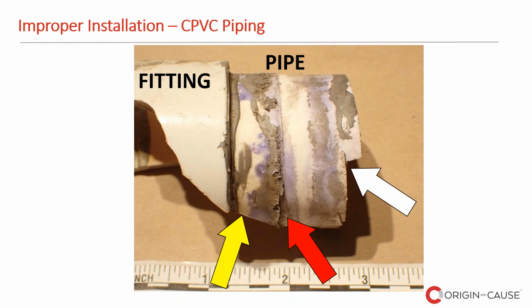In this case, you can see here with the red arrow, basically that's where the pipe was. So the pipe is the one with the purple cement, and the red arrow is the depth of insertion of that pipe into the fitting that's separated. You can see the white arrow showing that the pipe was cut really poorly. During the inspection, we found that it was not properly cut, not properly deburred, not properly chamfered. So a number of issues with that installation.